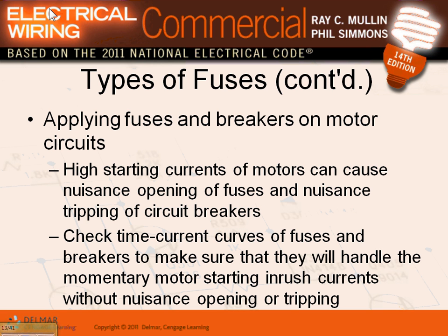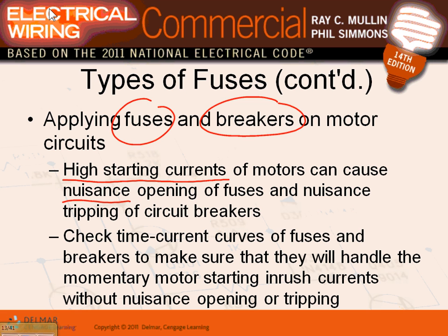Check the time curve. This is just a few things about when we deal with motors, guys. Every time you deal with fuses or circuit breakers on motors, you have to take into consideration the high starting current of a motor and nuisance tripping. The last thing you want is a circuit breaker that trips every time you start the motor. You look like you don't know anything about electrical design, right? So you have to size them. Be very careful when you size them. Next quarter, hold me accountable, guys.